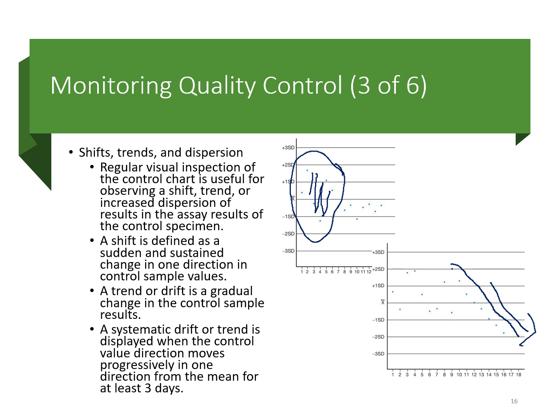Some of the things that we might need to look at will be the validity of that control sample. One thing we might do would be to make up a new control material to see if the integrity or validity of that particular material in that control matrix is starting to deteriorate. Maybe it's getting close to its expiration date, so there could be a variety of factors. Or maybe you've got a lamp in your machine that's starting to go bad, and so maybe you need to change that lamp. When we talk about this top figure here, you can see where it's sporadically all over the place, and then it levels out.